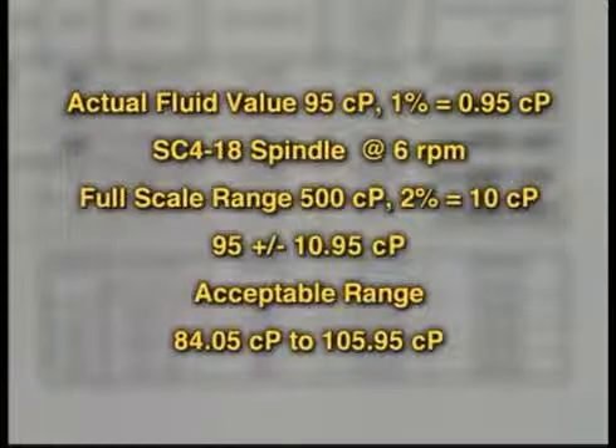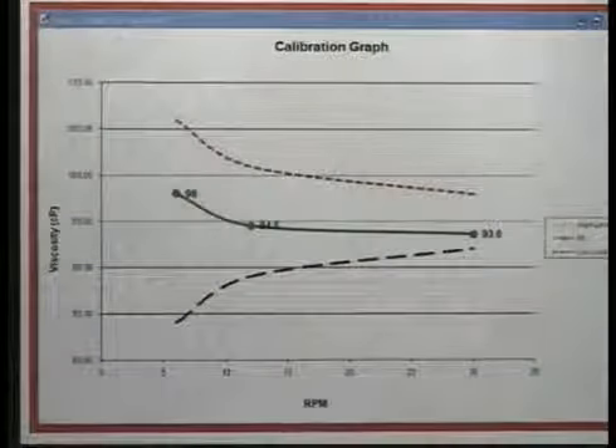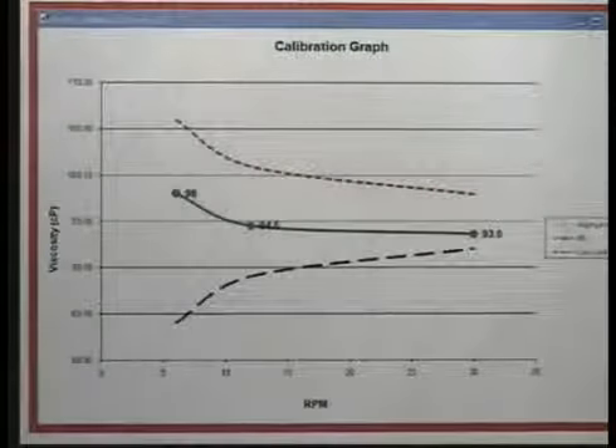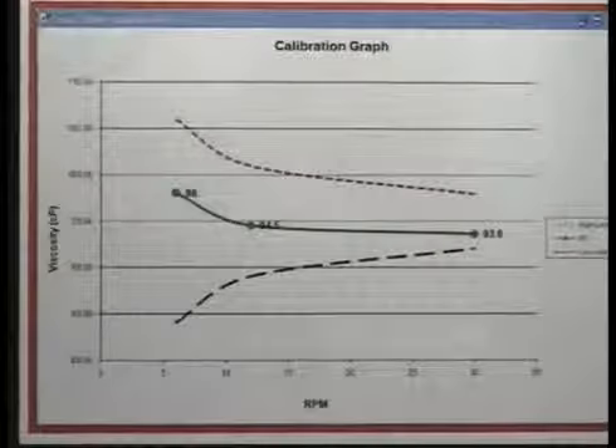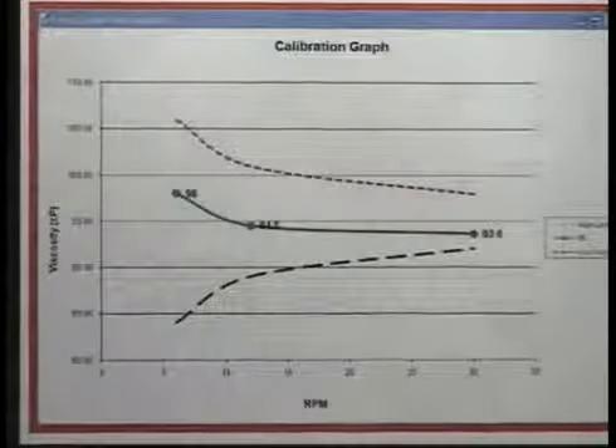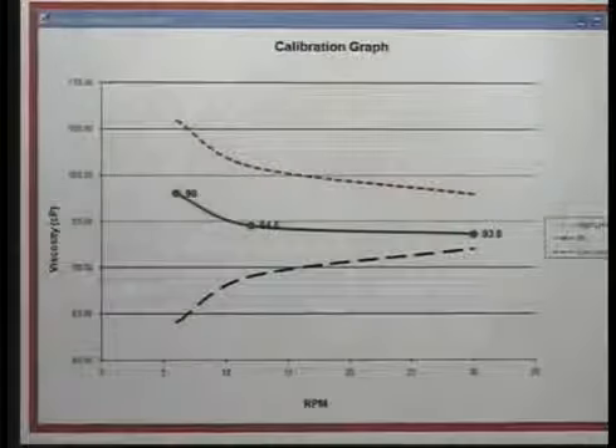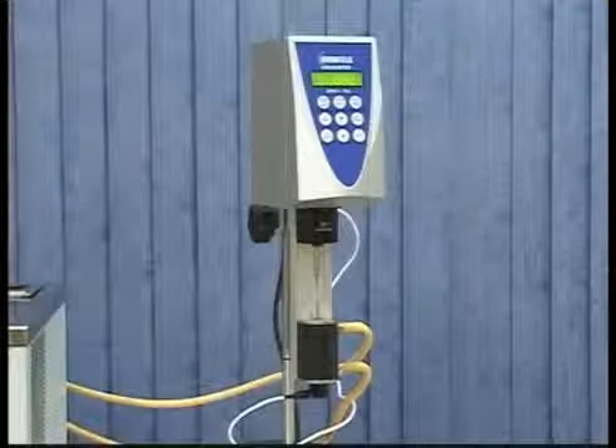Simply put, if the actual fluid value is 95 centipoise, 1% of this value is 0.95 centipoise. At a speed of 6 RPM, the full-scale range is 500 centipoise, and 2% of this value is 10 centipoise. Thus, the tolerance on the fluid at this speed with this SC4-18 spindle is 95 centipoise, plus or minus 10.95 centipoise. You can see a graph of your results with this worksheet and the tolerances. Select the Calibration Graph tab to view the results. The data points are plotted and upper and lower tolerances shown. In this example, you can see the data points came within tolerance. And that's it. You have performed a calibration check.